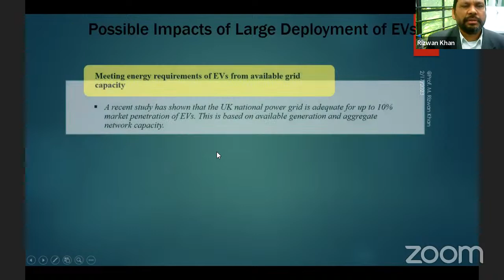Now, another possible impact of large deployment of EVs on the grid. If you are making more and more electric vehicles, you are deploying the vehicles, so what will be the possible impact on the grid? Meeting every energy requirement of EVs from available grid capacity: a study has shown that the UK national power grid is adequate up to 10% market penetration of EVs. So the following need to be appropriately assessed: uncontrolled loading due to increased deployment of EVs, change in voltage profile and violation of statutory limits, phase imbalance, reverse power flow, interference with the network protections.